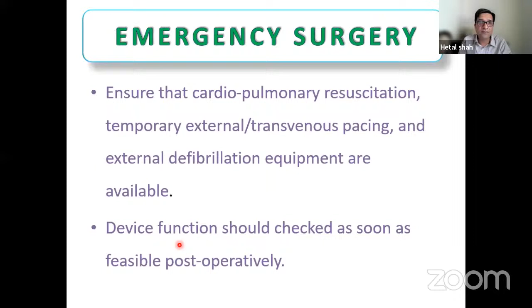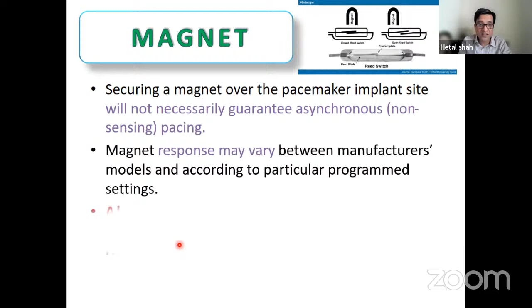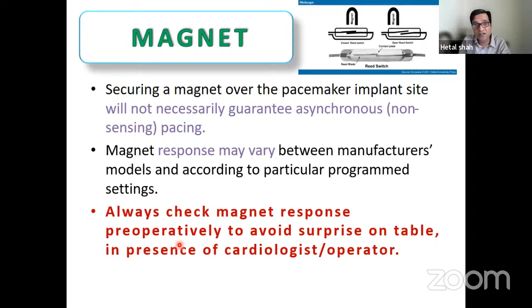Something about the magnet. A magnet is a device which you can secure over the pacemaker implant site, and usually it leads to the asynchronous mode, but it does not necessarily guarantee asynchronous mode always, and the response can vary according to the manufacturer and models. So it is very, very important that you check the magnet response pre-operatively to avoid surprises on the table, and it should be done ideally in the presence of a cardiologist or the device company representative, right?